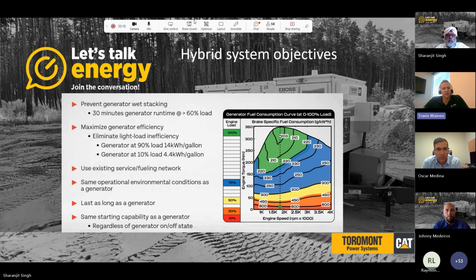The second objective is let's try to maximize that generator efficiency. If you look at the fuel burn curve of a generator, like on the right here, it's at 1800 RPM, which is 60 hertz, what we use here. If you're running that engine at 10% load, you're getting, I like to call it the fuel mileage of power generation, where you're talking in terms of output energy delivered per gallon of diesel that you put into the equipment. So at 10% load, that metric on a standard generator is about 4.4 kilowatt hours of energy per gallon of diesel that goes into that gen.